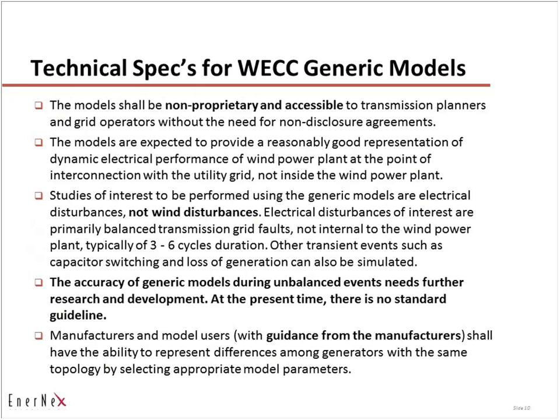A couple of things about the WECC generic model specifications are really important. The fact that these models are nonproprietary and accessible without NDAs or other restrictions is critical to the whole notion behind generic models. Furthermore, these models were developed to represent the behavior of the variable generation plant in response to grid disturbances, not renewable fuel disturbances. There's an assumption that solar irradiation or average wind speed across the plant is essentially constant over the timeframe of the simulation, which may not always hold as we move into validation.